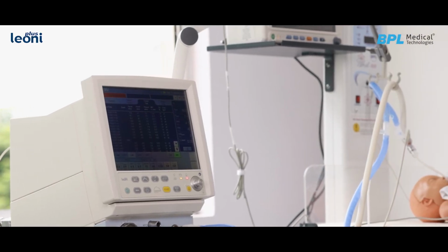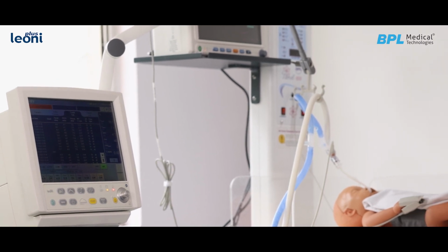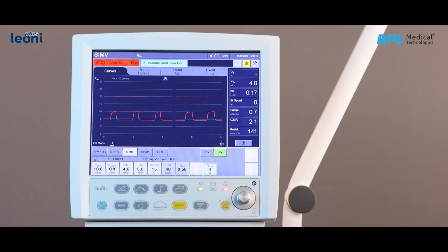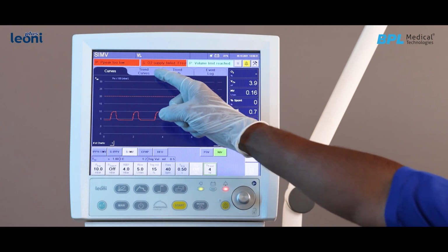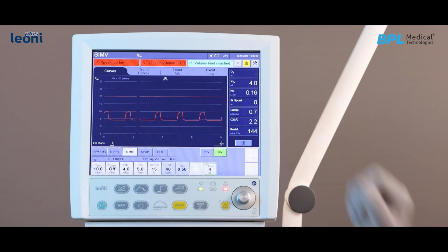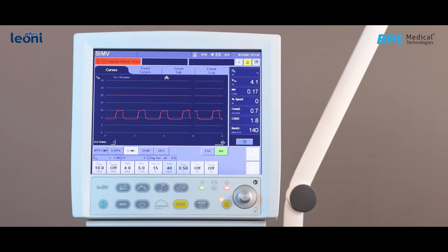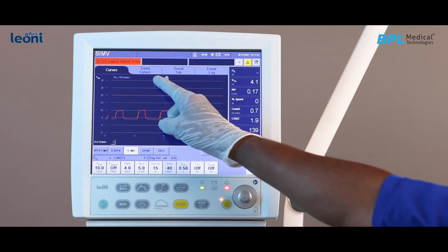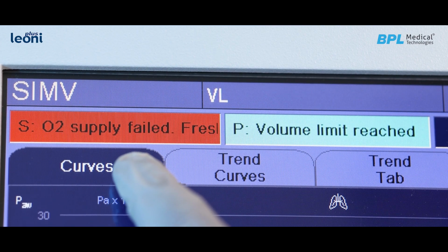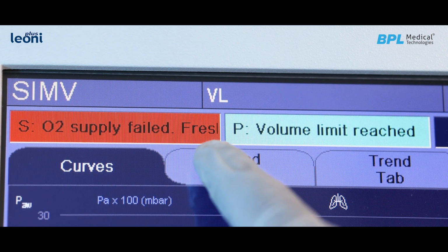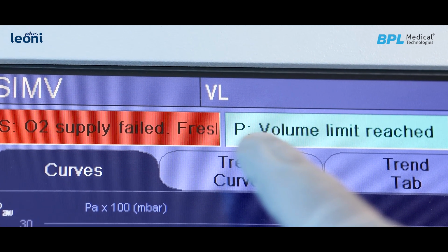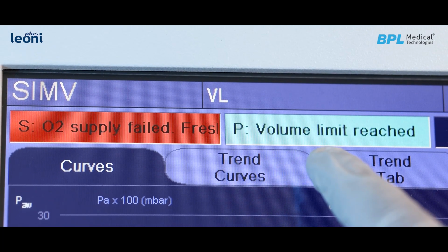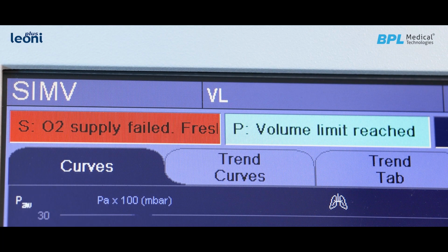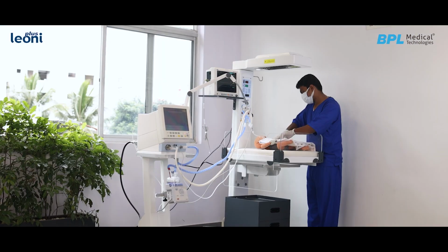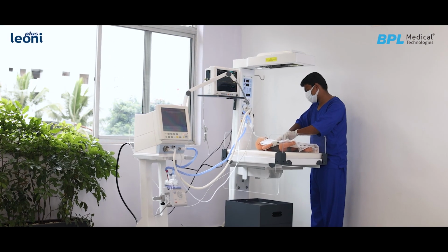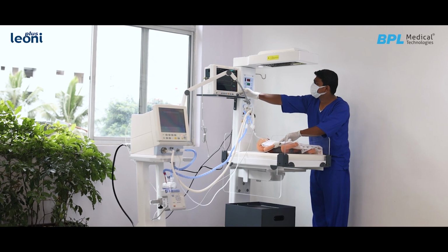Leoni Plus HFO features visual and audible alarm as per IEC standards. Alarms are categorized into 2 levels: high priority alarms and indicative alarms. It can be differentiated by looking at the display for message and hearing the alarm tone. High priority alarms are shown in red color with a longer tone so that it immediately captures the user's attention. Indicative alarms are shown in different color with a shorter alarm tone. Alarm volume will automatically be adjusted with respect to ambient noise in NICU.